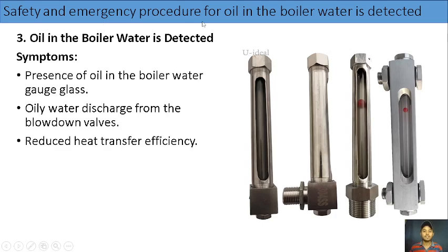So safety and emergency procedure for when oil in the boiler water is detected. Symptoms: presence of oil in the boiler water gauge glass. This is a gauge glass. If there is oil in your gauge glass, then there should be oil in your water. Oily water discharge from the blowdown valves. Reduced heat transfer efficiency. Those are the symptoms.